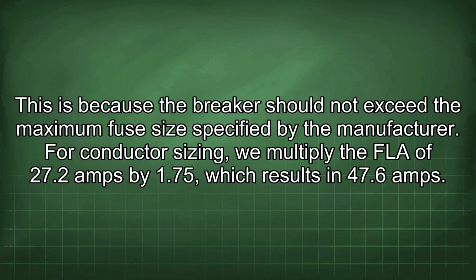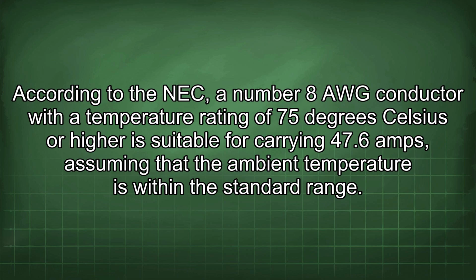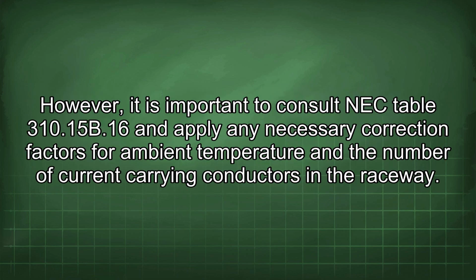For conductor sizing, we multiply the FLA of 27.2 amps by 1.75, which results in 47.6 amps. According to the NEC, a number 8 AWG conductor with a temperature rating of 75 degrees Celsius or higher is suitable for carrying 47.6 amps, assuming that the ambient temperature is within the standard range. However, it is important to consult NEC Table 310.15(B)(16) and apply any necessary correction factors for ambient temperature and the number of current carrying conductors in the raceway.